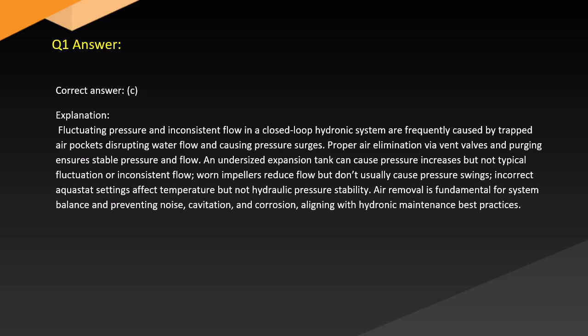An undersized expansion tank can cause pressure increases, but not typical fluctuation or inconsistent flow. Worn impellers reduce flow, but don't usually cause pressure swings. Incorrect aquastat settings affect temperature, but not hydraulic pressure stability. Air removal is fundamental for system balance and preventing noise, cavitation, and corrosion, aligning with hydronic maintenance best practices.